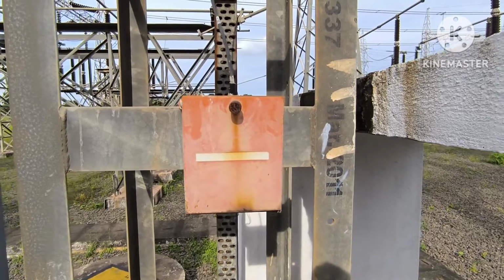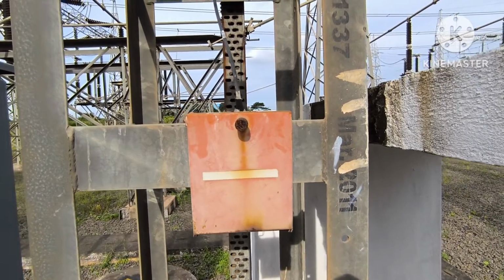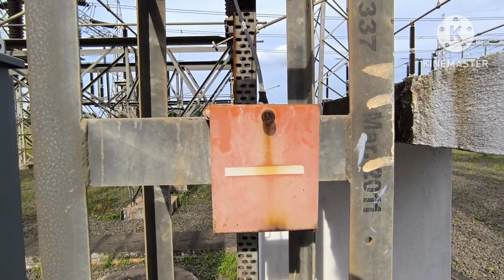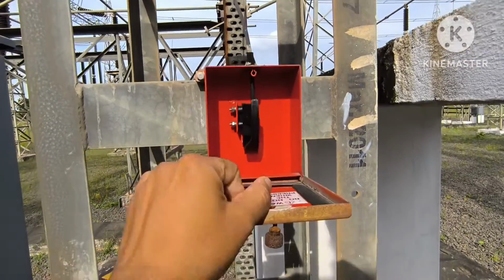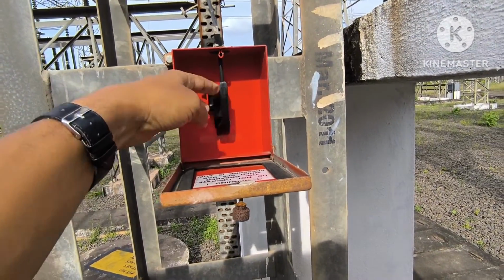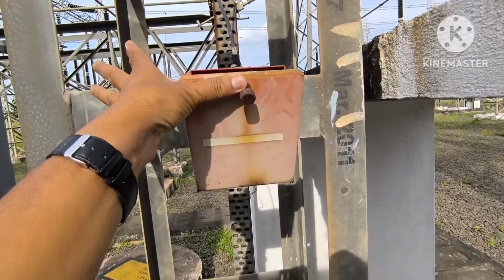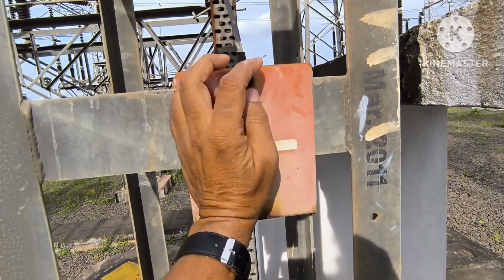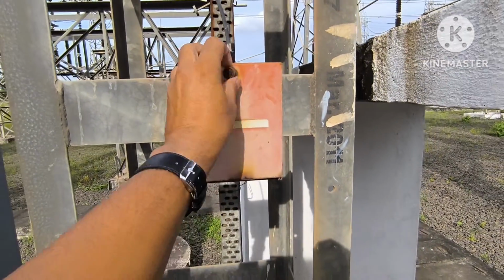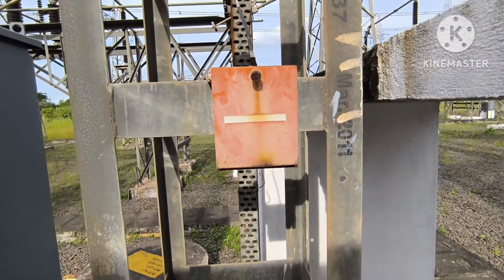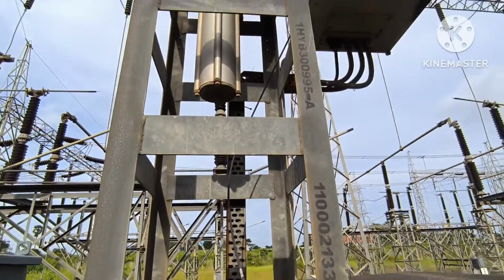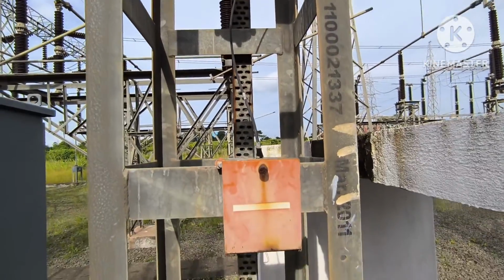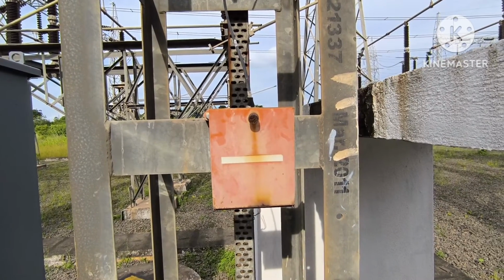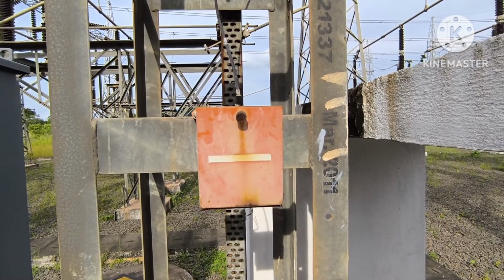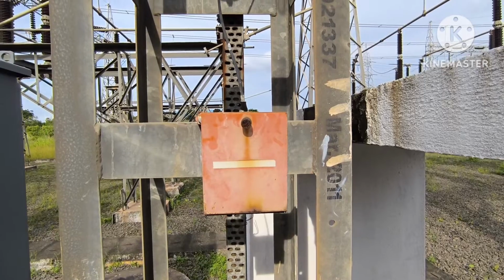This is the emergency lever given, so mechanically we can trip the breaker. This type of lever will be there. If you pull it, the breaker will trip automatically. If one pole trips, the remaining poles will automatically trip. This emergency lever is directly connected to the breaker tripping coil mechanism itself. So it is not electrical, it is a mechanical type of operation.